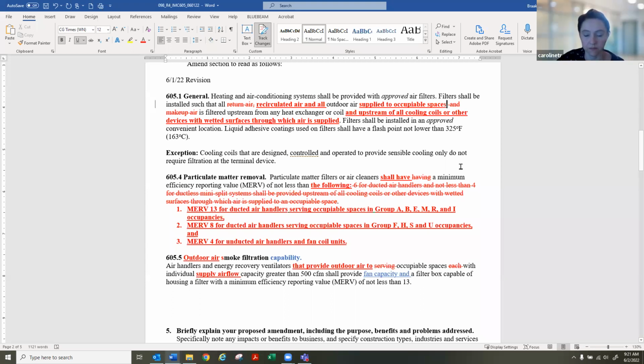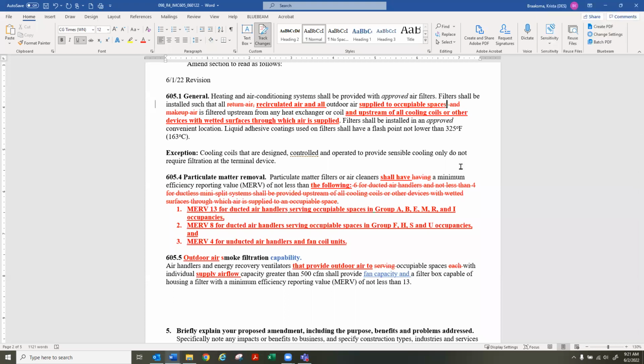Mike, go ahead. Thank you, Mike, for sharing these revisions. My question is kind of similar to Eric's. Just trying to understand, for a dwelling unit, for example, that would be an R2, you've got this particulate matter removal requirement in 605.4 that presumably would apply to the heating and cooling system air handlers. And then it doesn't seem like that would apply to outdoor air ventilation systems, which would fall under 605.5, and only apply if you've got greater than 500 CFM required or provided through the system, and would not apply to supply systems either. I was just wondering if you could speak to that and what your intention is.